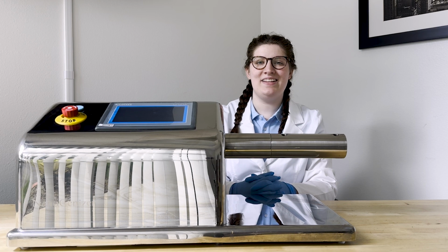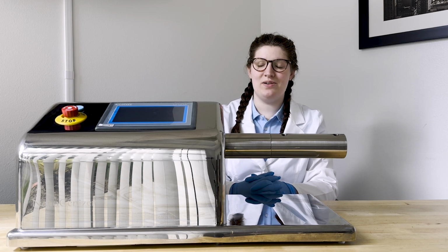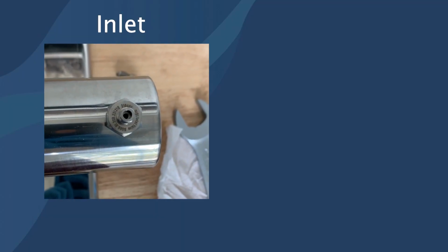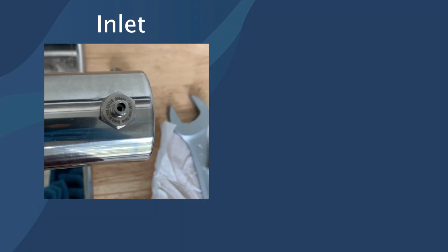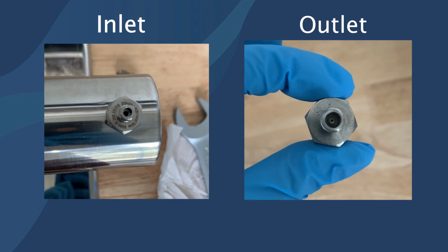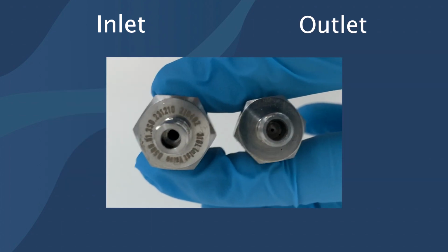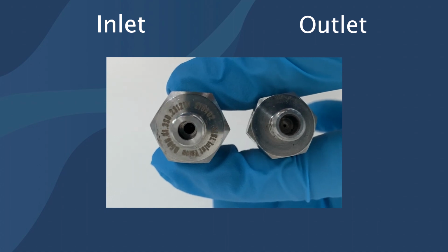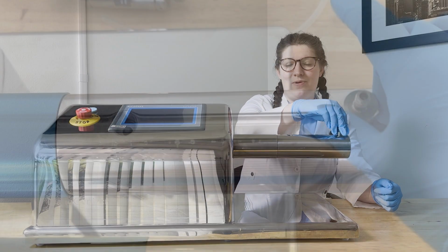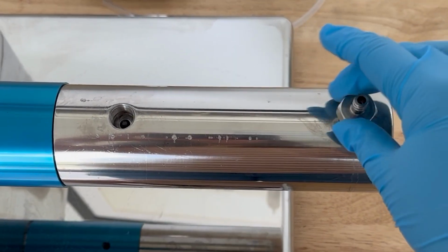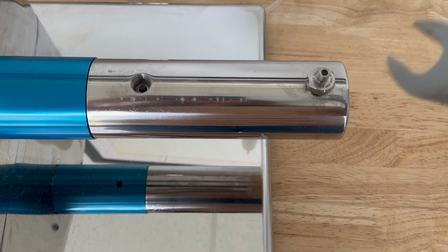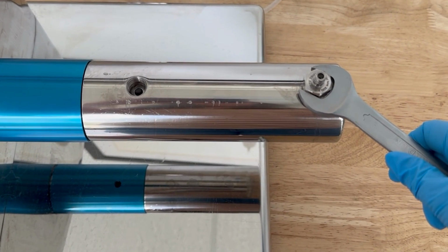The outlet and the inlet valve are important to distinguish because they allow liquid flow in opposite directions. The inlet valve will have a laser marking indicating that it is the inlet. The outlet valve will be blank. There is also a slight size difference between the two valves. The inlet valve screws clockwise into the arm of the equipment. You can finish tightening using the wrench that will come with your setup kit.